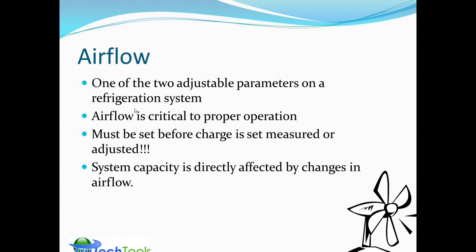Airflow is one of the two adjustable parameters on an air conditioning or refrigeration system. We all realize proper airflow is critical to getting conditioned air to the space. To actually remove humidity, drop temperature, or increase temperature, you have to have the proper CFM flowing through the system. In an air conditioning system, airflow must be measured, set, and adjusted before you set the refrigerant charge — if you don't set airflow first and you're adjusting charge, you're wandering down an aimless path.